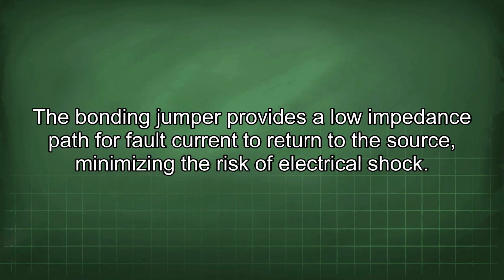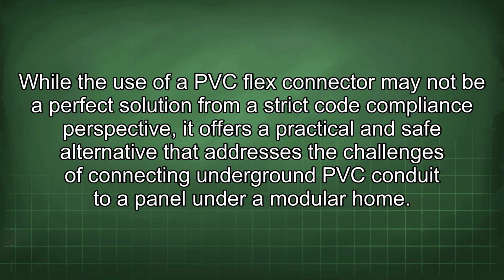The bonding jumper provides a low impedance path for fault current to return to the source, minimizing the risk of electrical shock. While the use of a PVC flex connector may not be a perfect solution from a strict code compliance perspective, it offers a practical and safe alternative that addresses the challenges of connecting underground PVC conduit to a panel under a modular home.